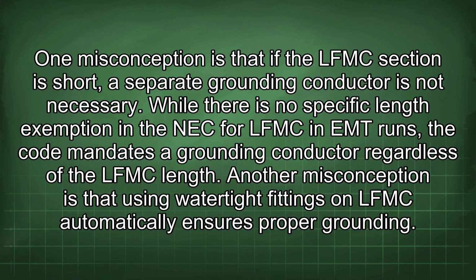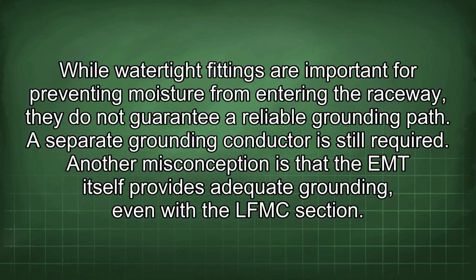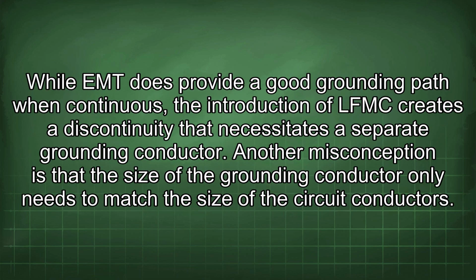Another misconception is that using watertight fittings on LFMC automatically ensures proper grounding. While watertight fittings are important for preventing moisture from entering the raceway, they do not guarantee a reliable grounding path. A separate grounding conductor is still required. Another misconception is that the EMT itself provides adequate grounding, even with the LFMC section.